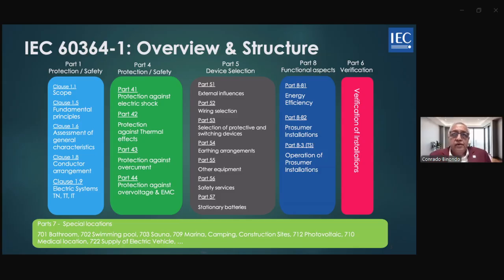Then after that, we have part 5, which is about device selection. In part 4, you have all the requirements of the standard, but in part 5, you have to apply or select the right devices for the installation. What is considered in part 5 is external influences, such as how ambient temperature and humidity will affect your installation.